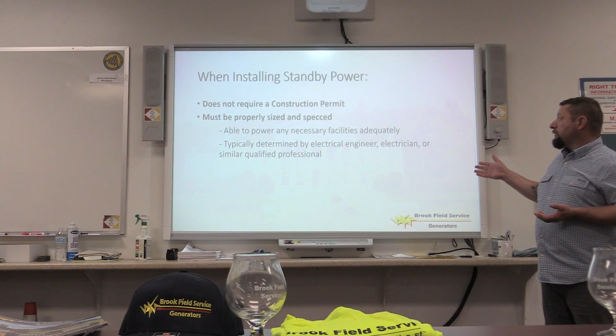You don't want to get a generator where you can only run part of your system. If you've got large pumps or large motors required for your plant to function and the generator doesn't run them, it's not really any good to you, because you can only operate for a certain amount of time before you need those. Typically for small sites, an electrician or someone who installs generators sizes it for you, or electrical engineers for larger ones, or someone similarly qualified.